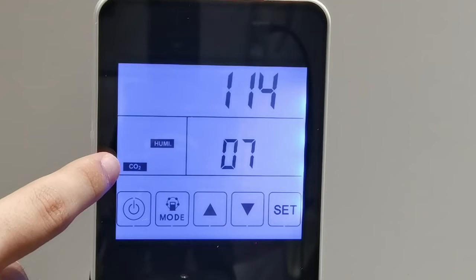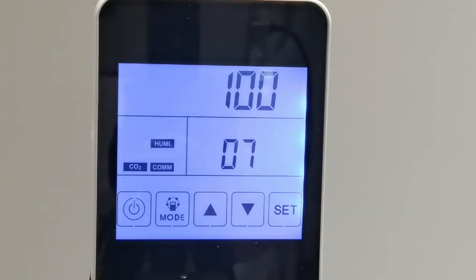The actual value is multiplied by ten. For example, if we want a concentration of 1000, we set 100. Press the down button, make sure it's 100, then press the set button. And when it shows 00, it means the CO2 function is in off state.